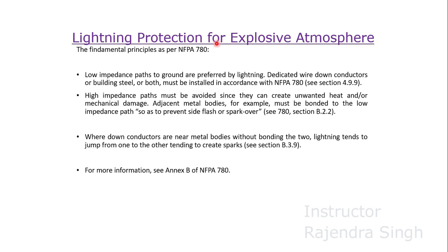Lightning protection for explosive atmospheres. IEC 62305 defines the external and internal lightning protection for equipment or structures. However, for explosive atmospheres, the design considerations for lightning protection shall be done either based on NFPA 780 requirements or based on the requirements of OISD 180.